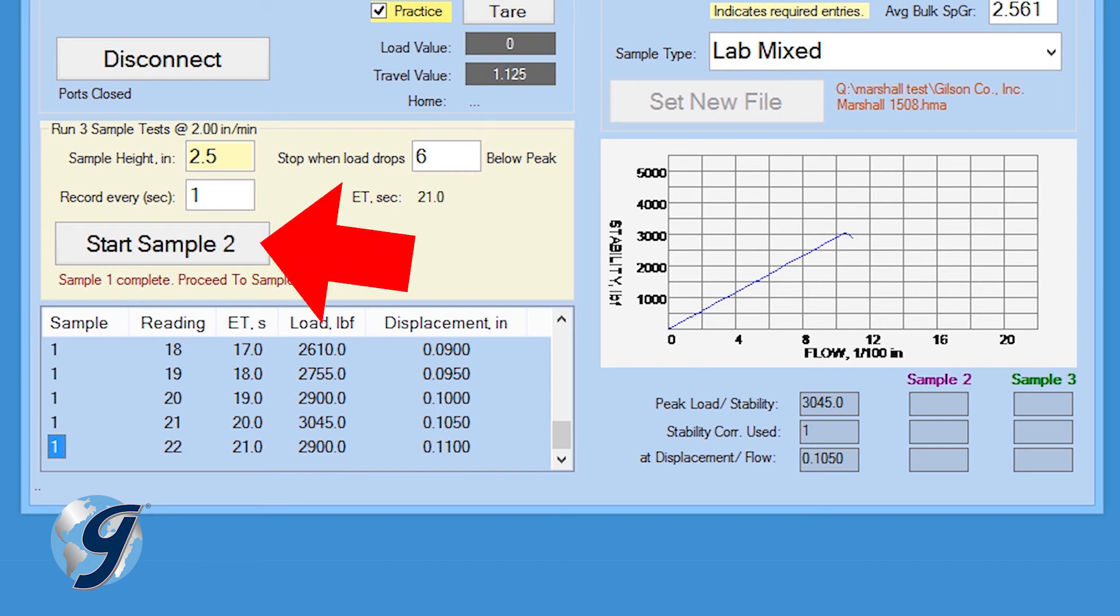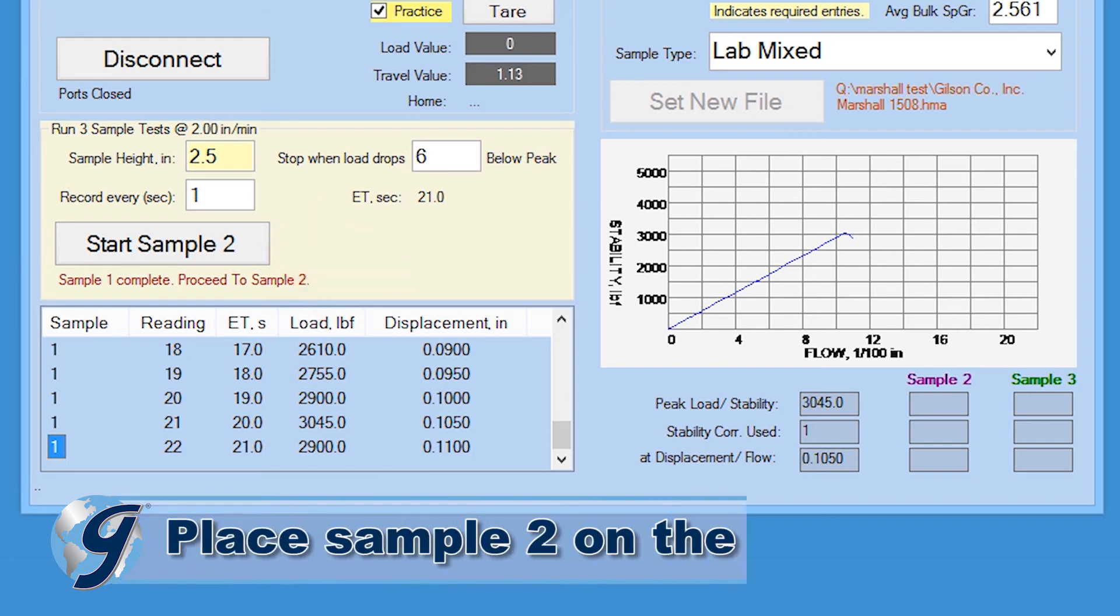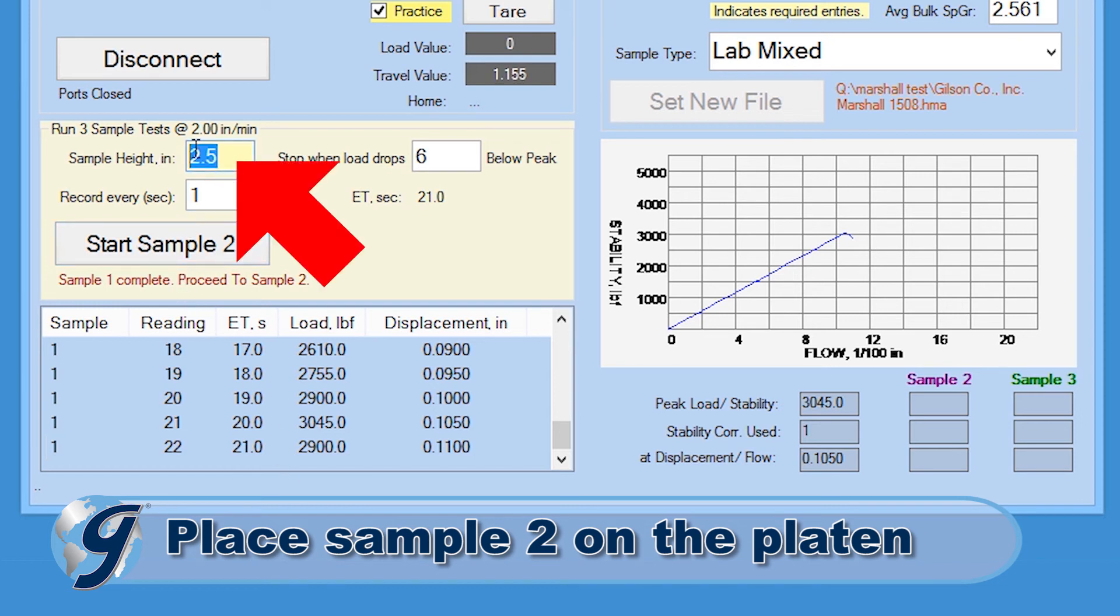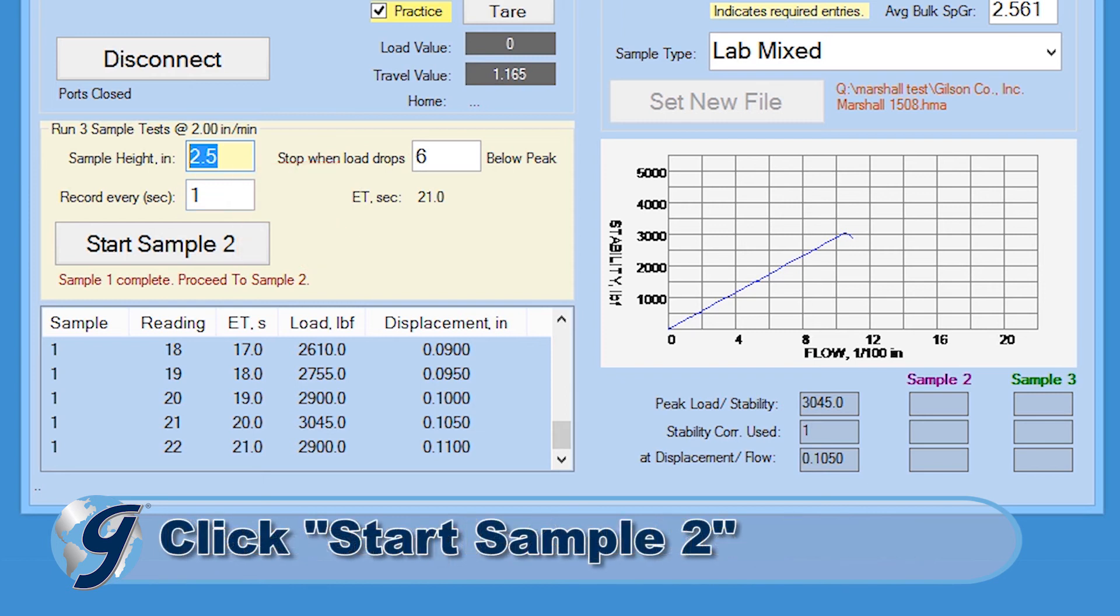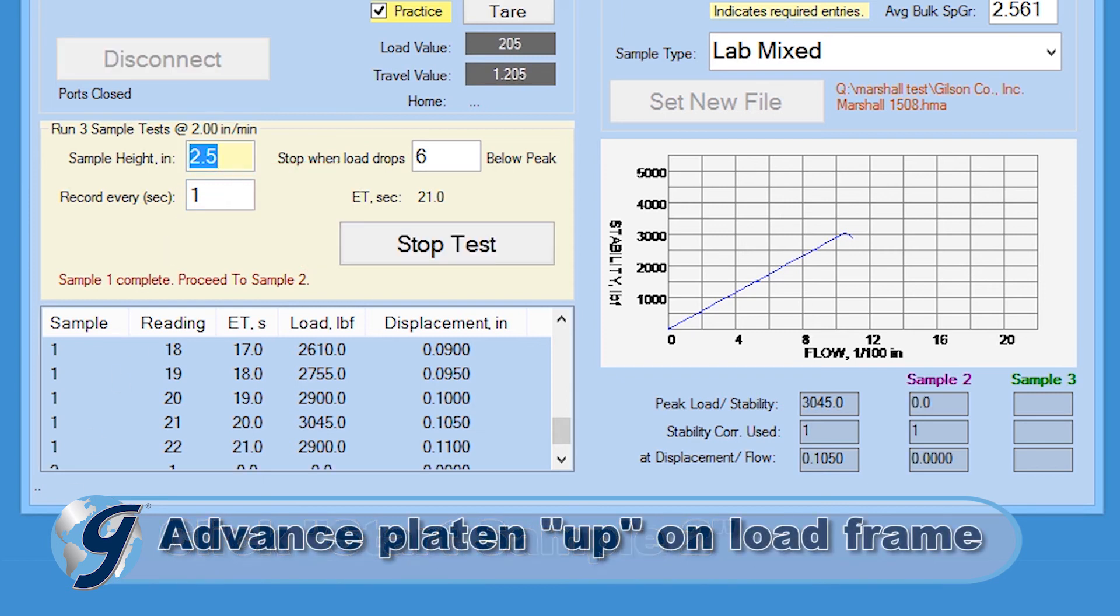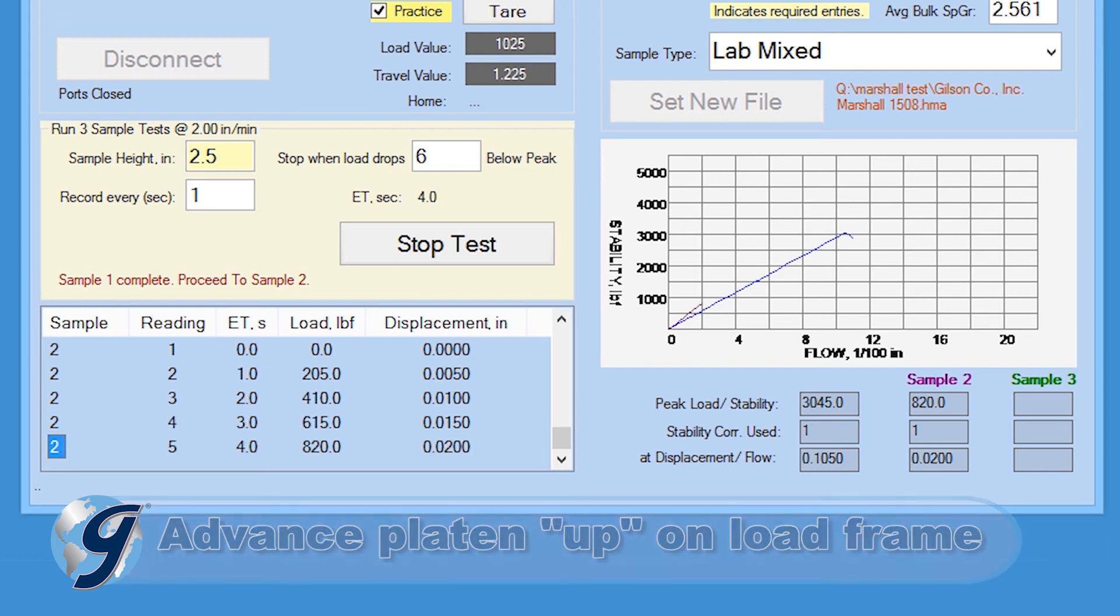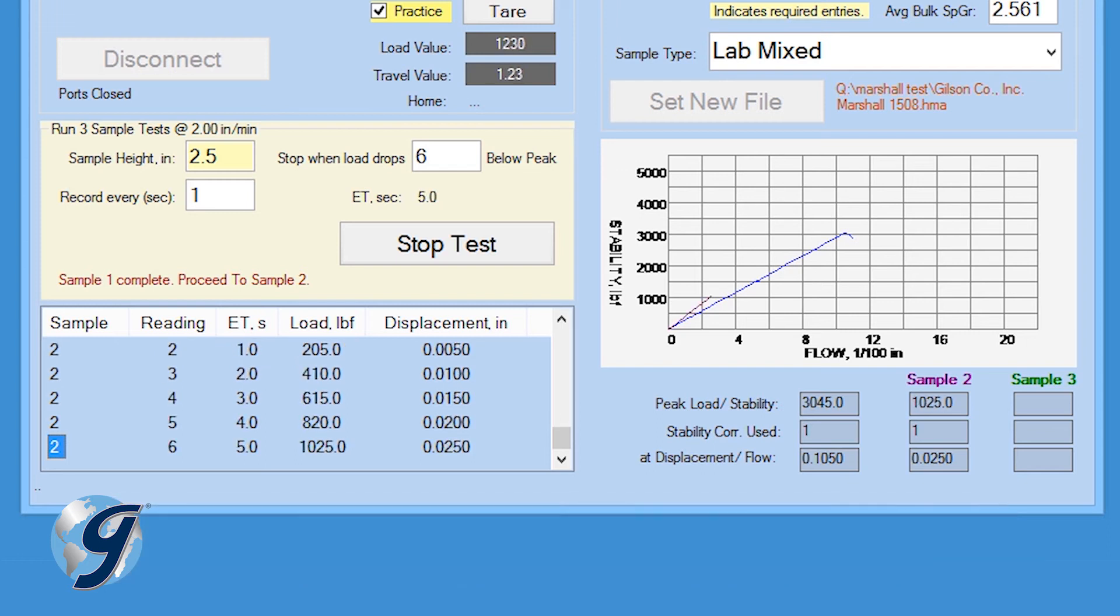A start sample 2 button will appear. Seat sample 2 on the platen. Change the sample height value in the sample test tile for the second sample and click start sample 2. Switch the platen advance to up on the load frame and the program will again begin recording data.